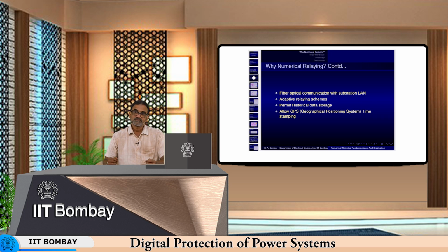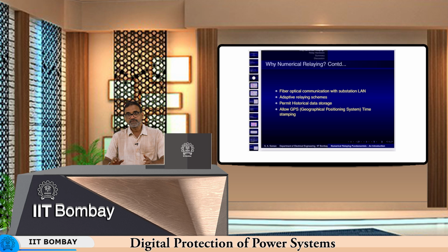One more advantage is adaptive relaying, either through some external input or through external data available from other relays. In an electromechanical relay, once you set the parameters, unless you went and changed it manually, there was no way to make it adapt to any kind of network situation or load situation.